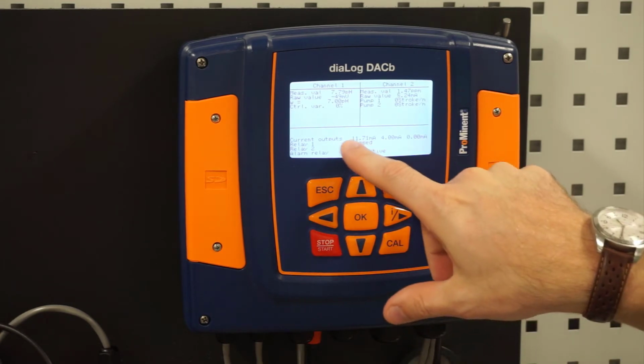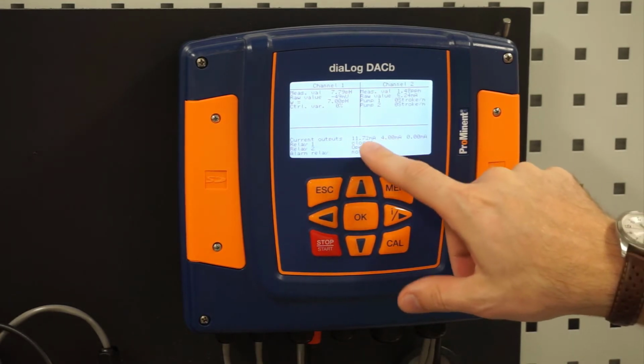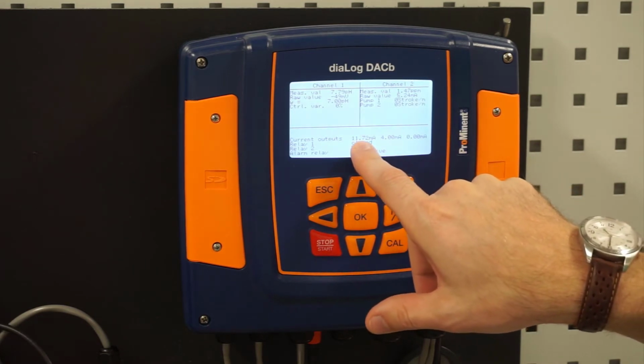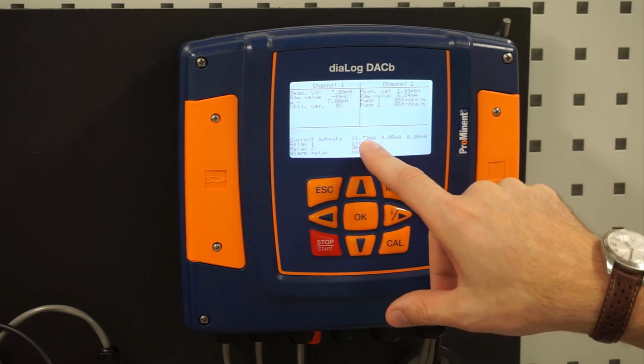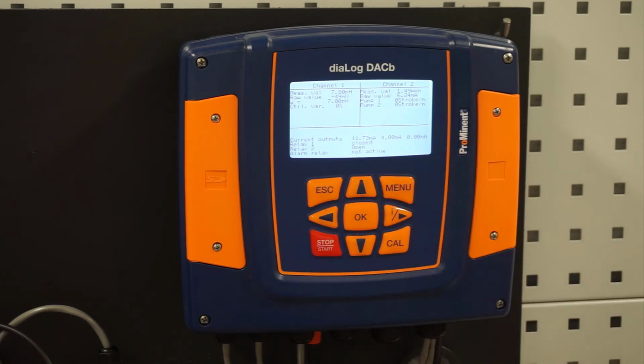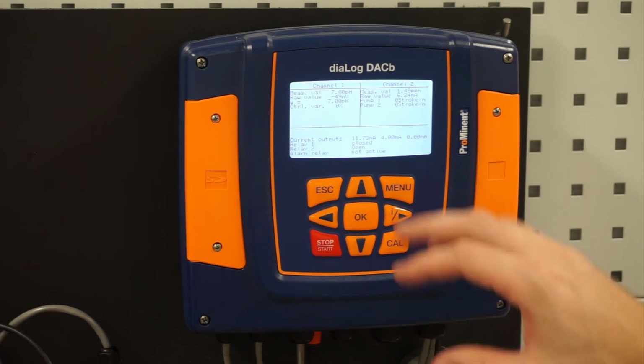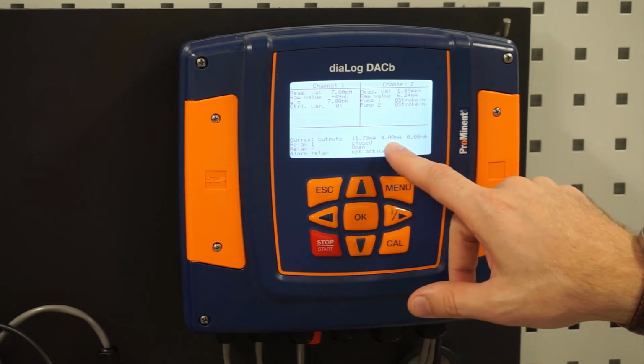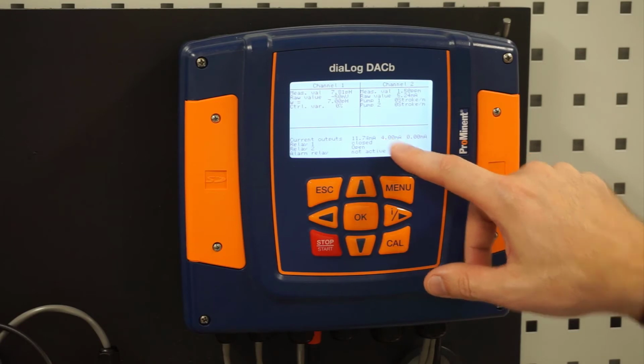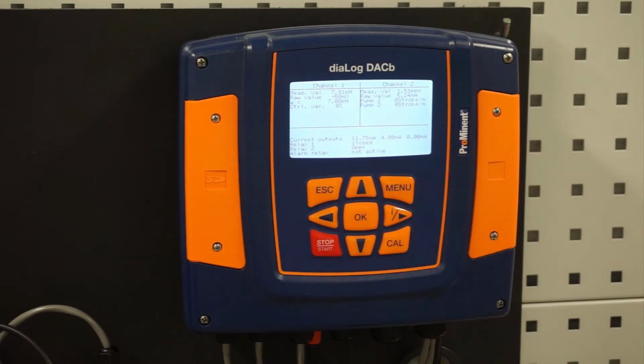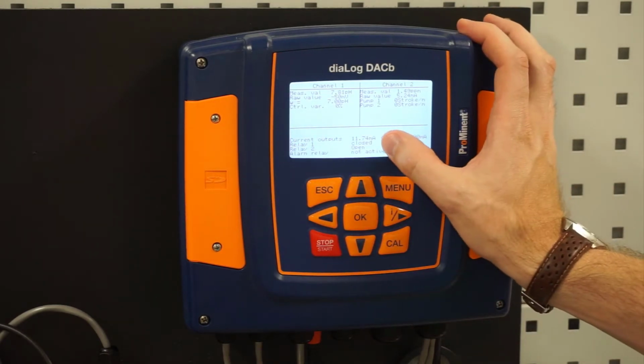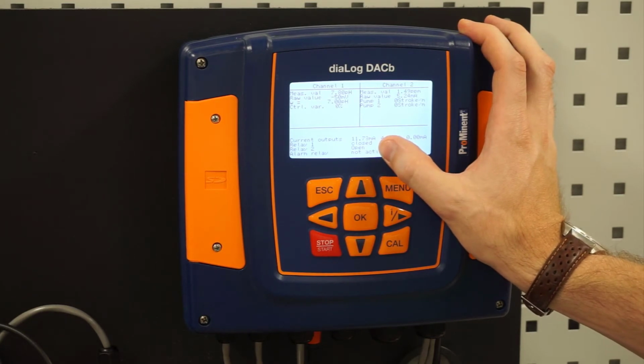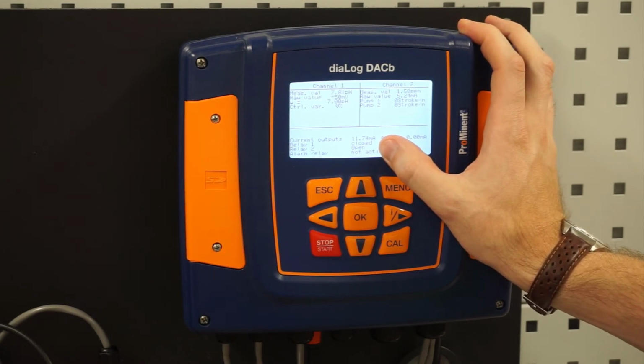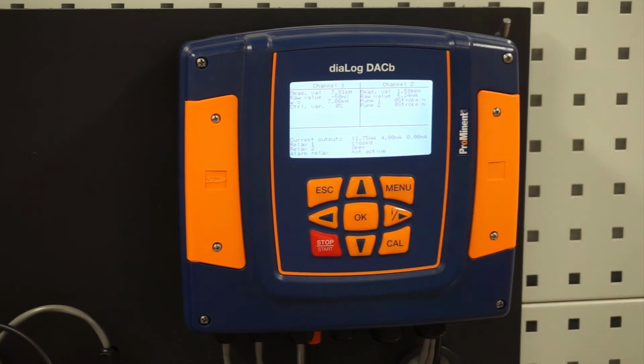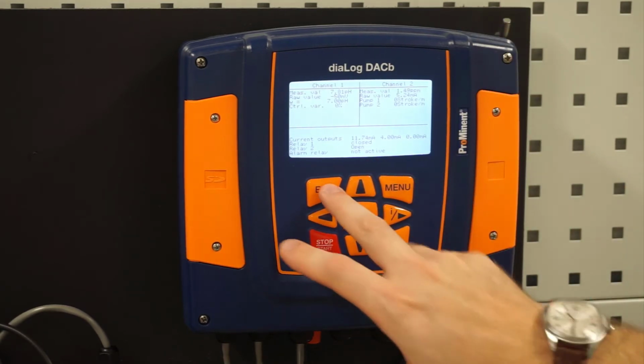You also see our current outputs. So we have 2 current outputs set up. One is sending 11.72 milliamps. That's most likely our acid pump, trying to drive down the pH value. And then we're doing 4 milliamps. I'll show you how to look to see what those are set up. We also have 2 relays here set up. Those are our limit relays. One is open and one is closed. And then we have an alarm relay. If I hit escape, that will back us out.